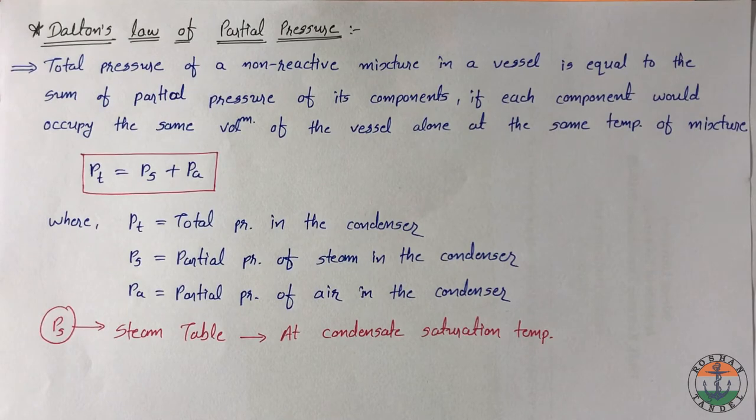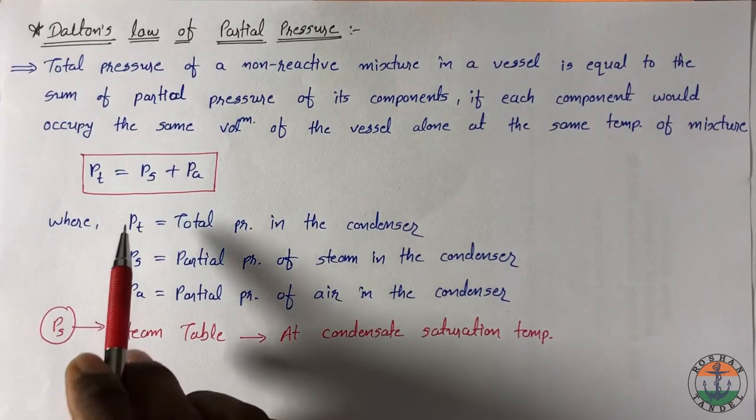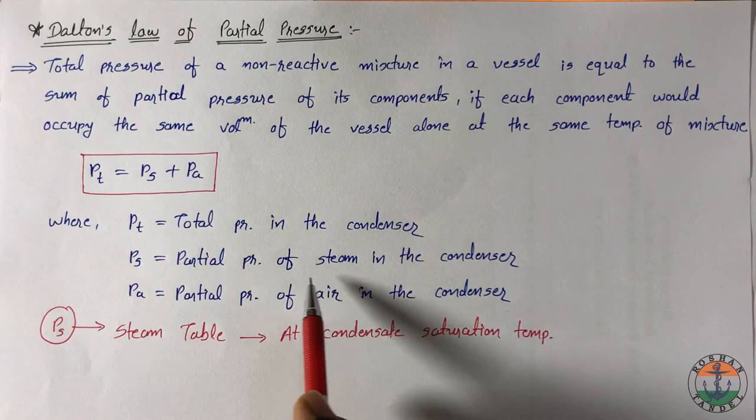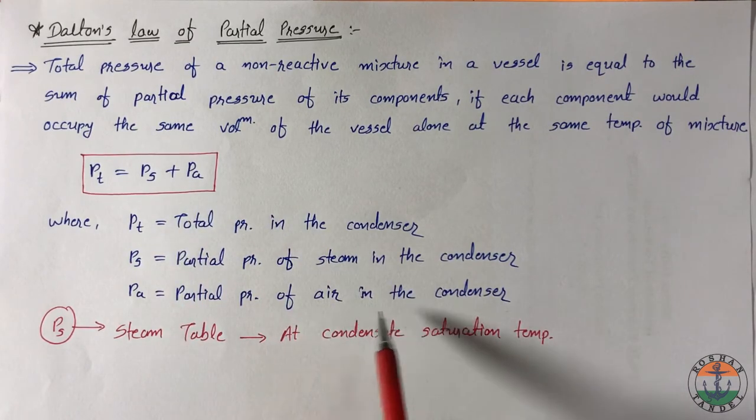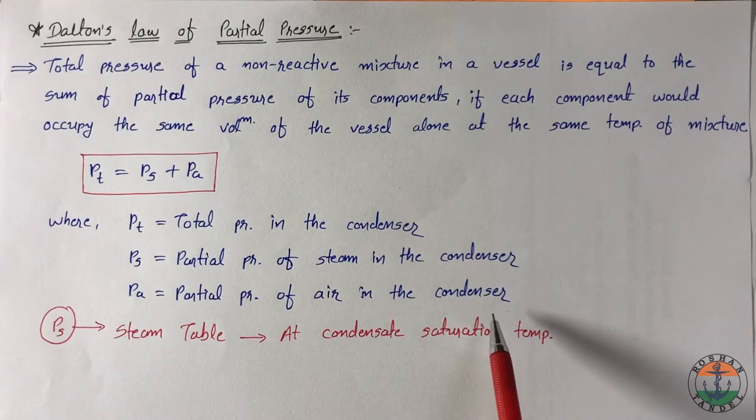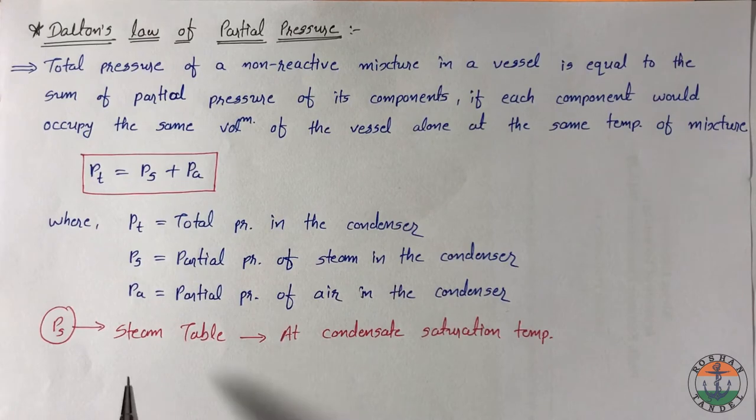Here in the condenser, some air is also present with the steam. So absolute pressure in the condenser is considered as total pressure in the condenser which is the sum of partial pressure of steam plus partial pressure of air present in the condenser. Here partial pressure of steam we can calculate from the steam table at condensate saturation temperature.